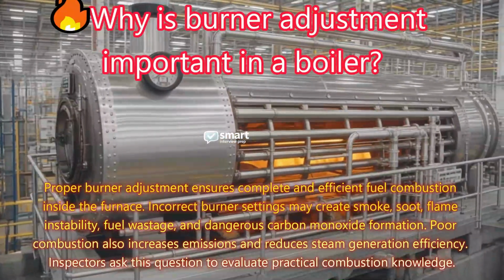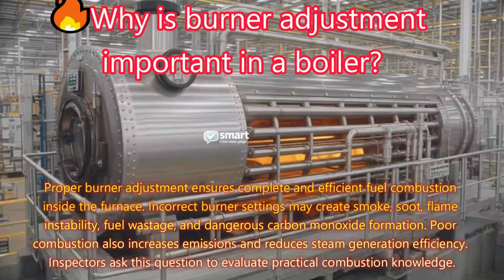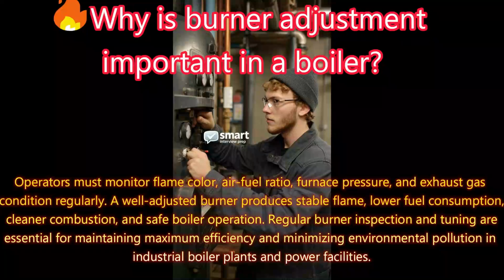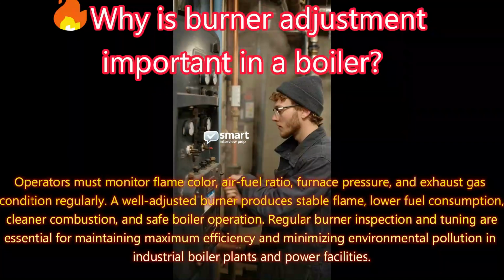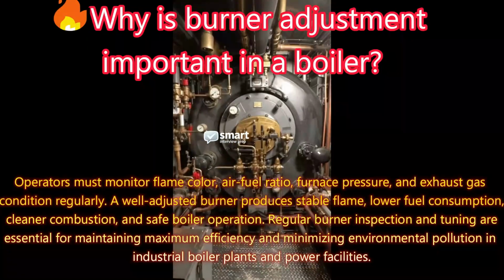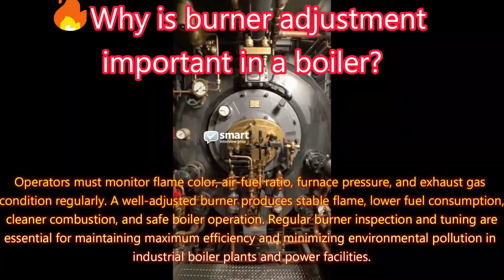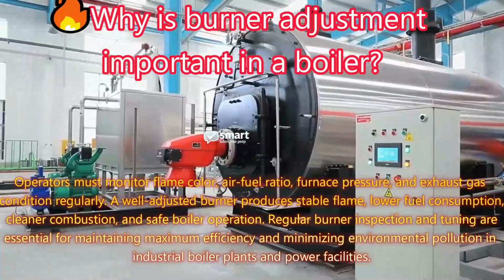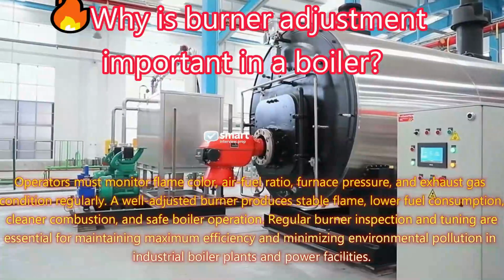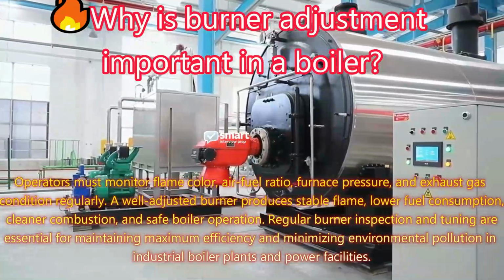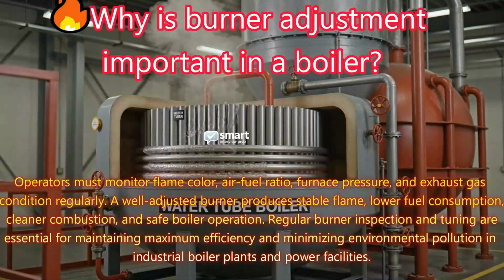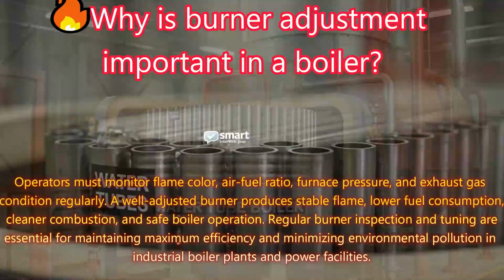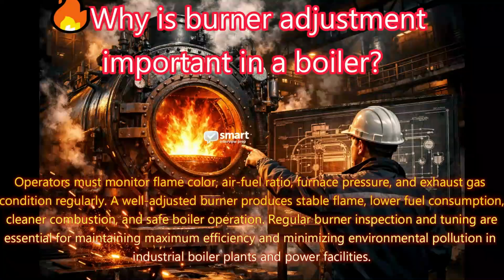Inspectors ask this question to evaluate practical combustion knowledge. Operators must monitor flame color, air-fuel ratio, furnace pressure, and exhaust gas condition regularly. A well-adjusted burner produces stable flame, lower fuel consumption, cleaner combustion, and safe boiler operation. Regular burner inspection and tuning are essential for maintaining maximum efficiency and minimizing environmental pollution in industrial boiler plants and power facilities.